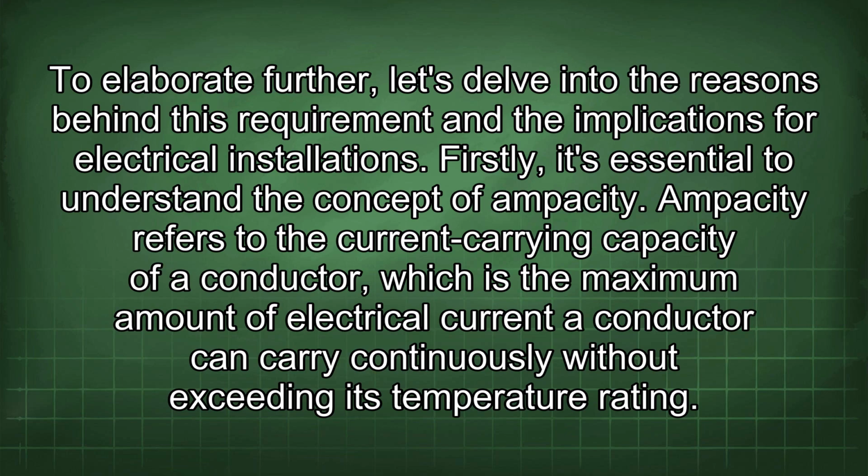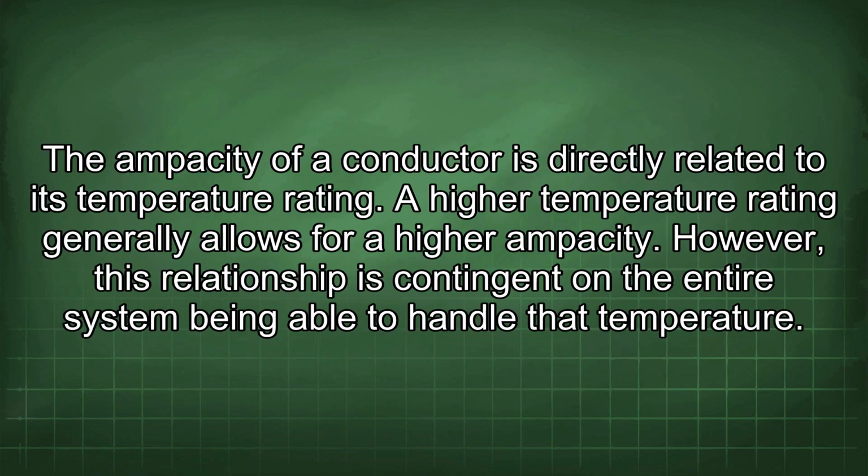Firstly, it's essential to understand the concept of ampacity. Ampacity refers to the current carrying capacity of a conductor, which is the maximum amount of electrical current a conductor can carry continuously without exceeding its temperature rating. The ampacity of a conductor is directly related to its temperature rating. A higher temperature rating generally allows for a higher ampacity. However, this relationship is contingent on the entire system being able to handle that temperature.